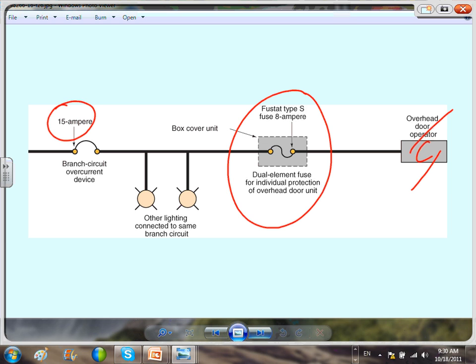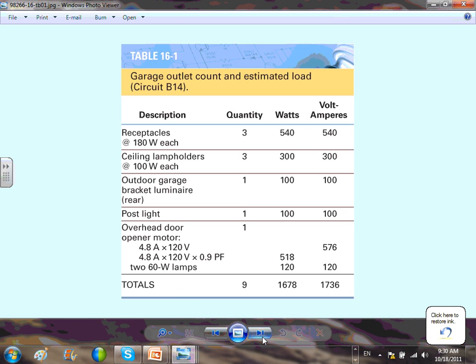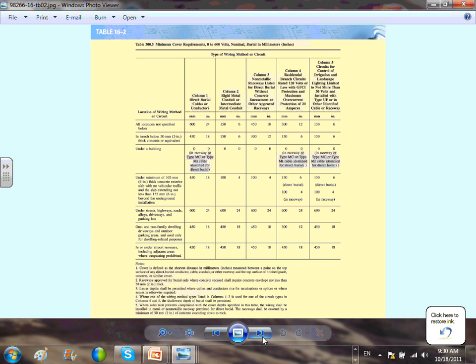Is it required? No. Is it good? Yes. Don't most of the motors have a built-in overload? They do have an overload in them. This is really a supplemental overcurrent protection device, mainly for short circuit, and if it's dual element, it will give you overload protection too. Calculating the circuit.